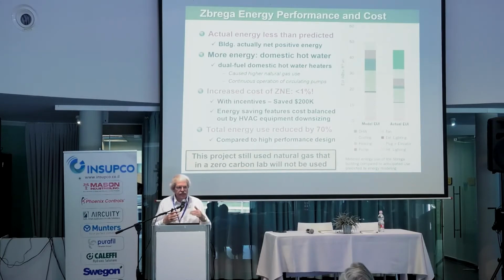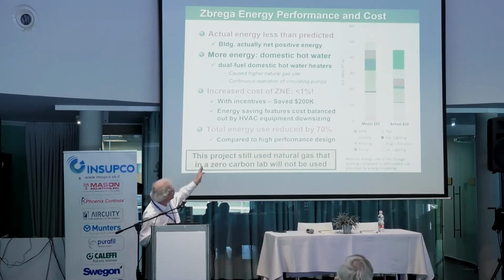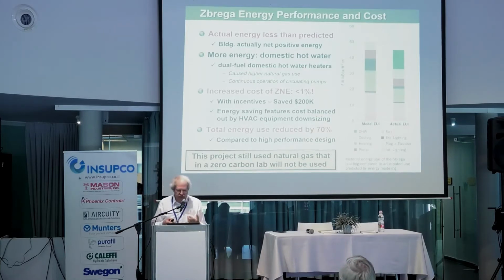The whole idea is that by reducing energy and airflow requirements, they could use a smaller HVAC system. They had to pay for extra controls, but that cost was basically covered by the reduction in HVAC system size, so net cost was roughly neutral, with just a very slight change. And total energy use was significantly reduced by about 70%.